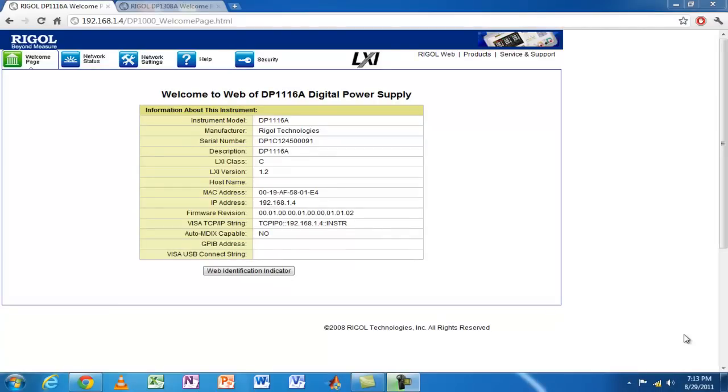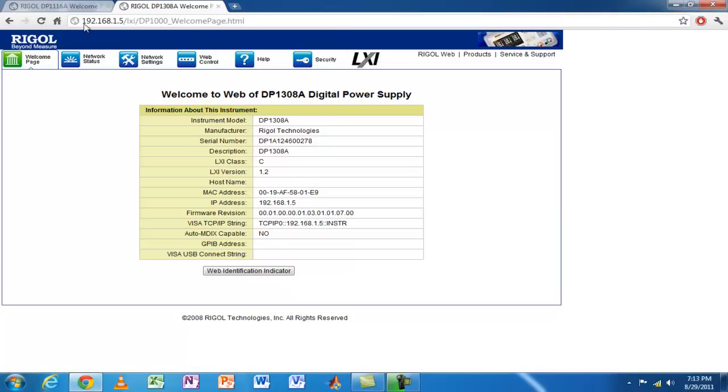I've connected both power supplies through the Ethernet port to a router, and I'm connected to the router using my laptop. I can go ahead and type the IP address of the first power supply and the second power supply, then connect to the built-in web interface for both of them.